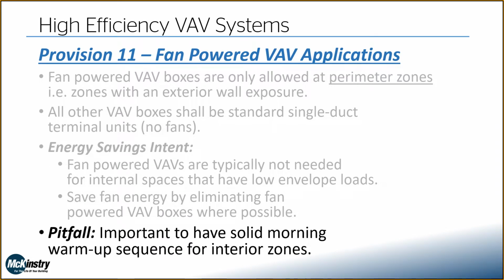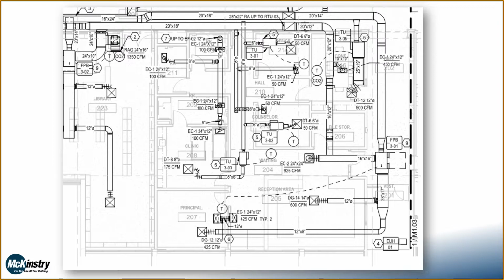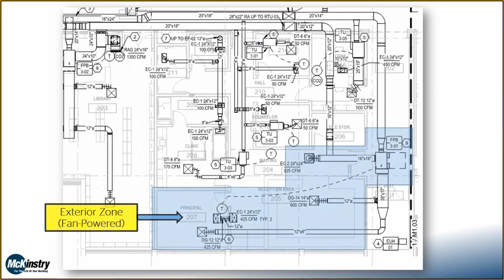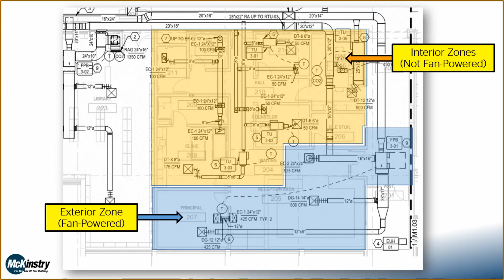But it is important to have a solid morning warm-up sequence for any of those interior zones. Sometimes those interior zones can have trouble heating up in a morning warm-up cycle without that fan assist. So you might have to get creative with your sequence to allow the boxes to increase to a higher primary air set point just to get better air distribution. Something to watch out for. To visualize that, here's an example of a VAV system we designed where we have an exterior zone. That's going to be a fan-powered box because the south exposure with all of that glazing makes it a perimeter zone. And all those VAV boxes on the inside, for our interior zones, are just standard terminal units with reheat.